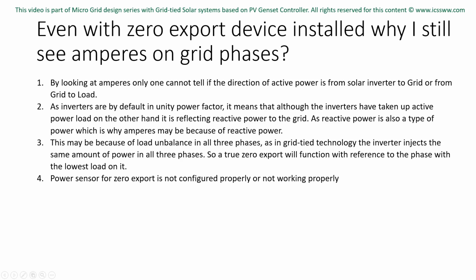Number 1, by looking at amperes alone, one cannot tell whether the direction of active power is from the solar inverter to the grid or from the grid to the load. Number 2, as inverters are by default in unity power factor, it means that although the inverters have taken up the active power load, on the other hand, they are reflecting reactive power to the grid. As reactive power is also a type of power, the amperes may be because of reactive power.